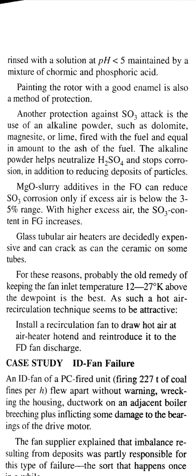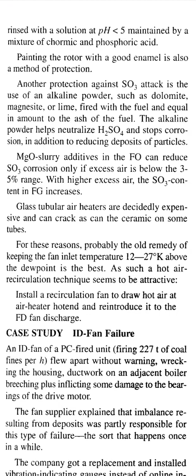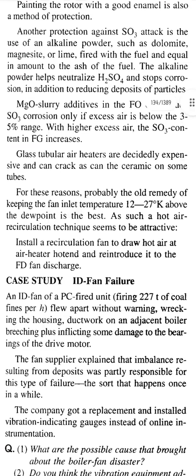Painting the rotor with a good enamel is also a method of protection. Another protection against SO3 attack is the use of alkaline powder such as dolomite, magnesite, or lime fired with fuel and equal in amount to the ash of the fuel. The alkaline powder helps neutralize the H2SO4 and stops corrosion, in addition to reducing deposition of particles.